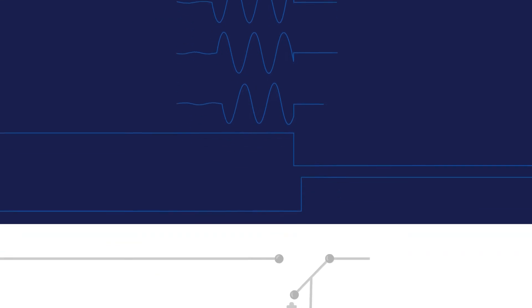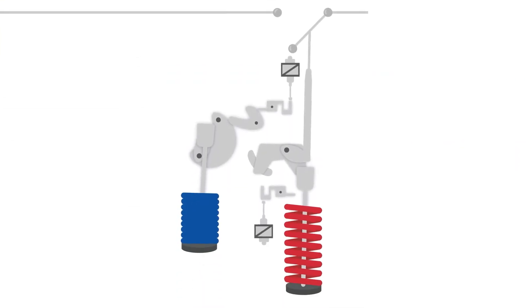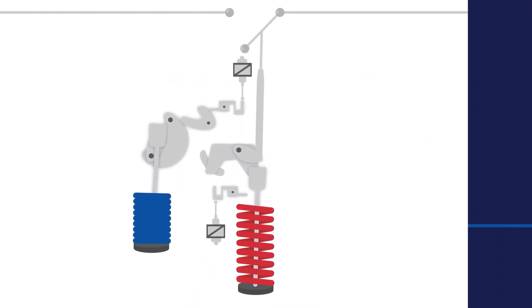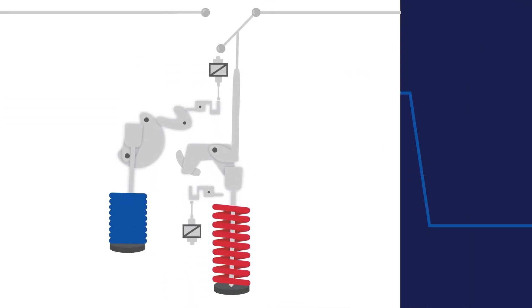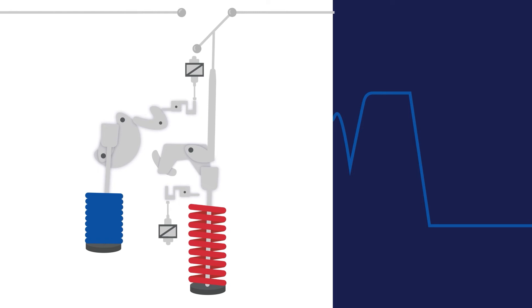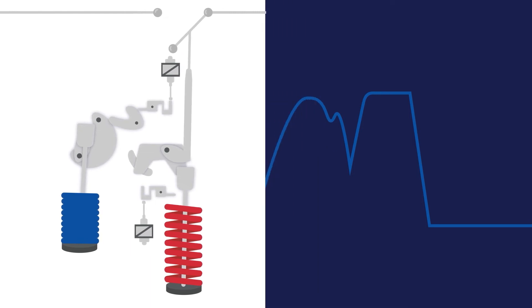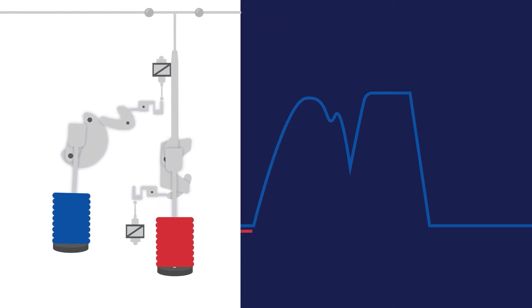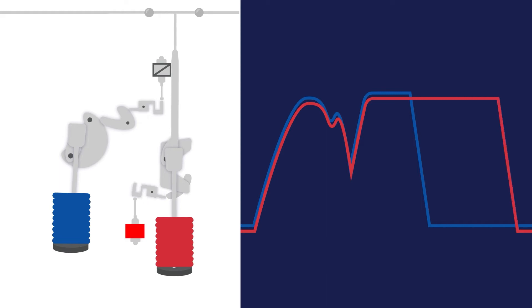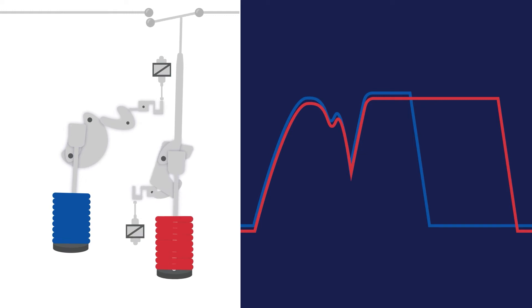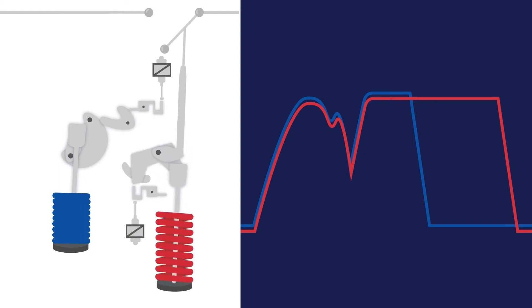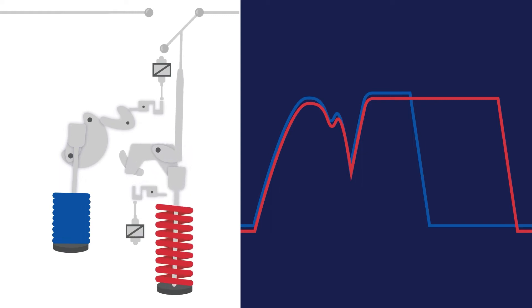This comes in handy when the lubrication deteriorates. The beginning of the waveform would overlay almost identically to the first operation through the point where the plunger strikes the buffer. However, the time which elapses until the falling edge of the coil current would increase. This increase would also be apparent in the amount of time it takes for current flow through the main contacts to cease.